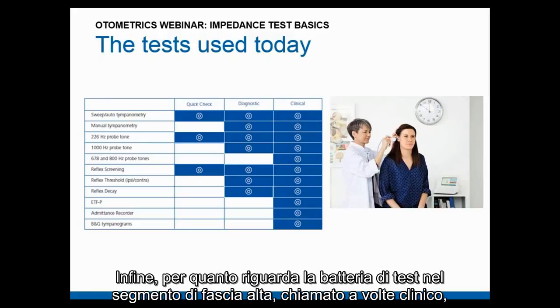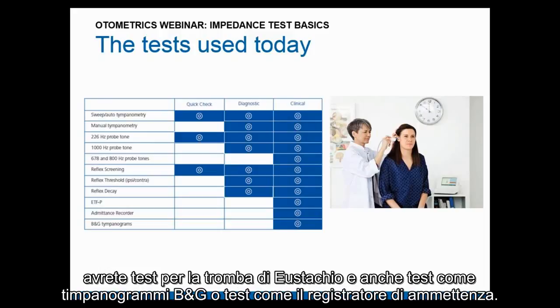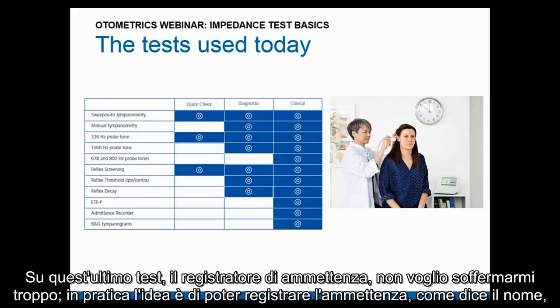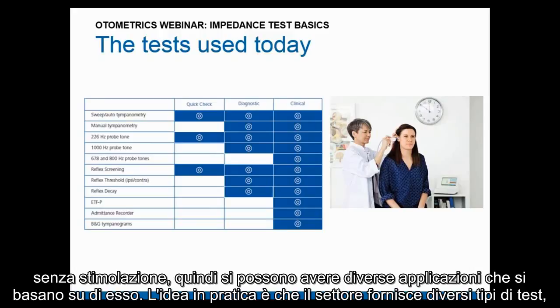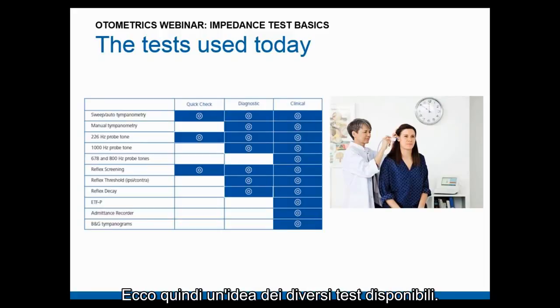In the high-end or clinical segment, you find all the tests described before, plus additional probe tones like 678 or 800 Hz, tests for the Eustachian tube, multi-frequency tympanograms, and the admittance recorder. The admittance recorder allows recording of admittance without stimulation. The industry provides increasing test capabilities as you move up through the segments, with the high-end offering as much as possible.